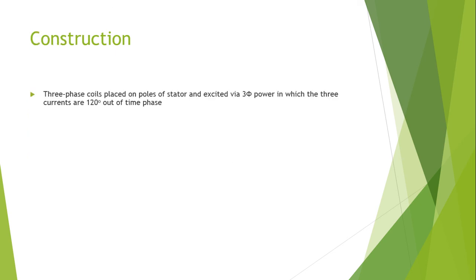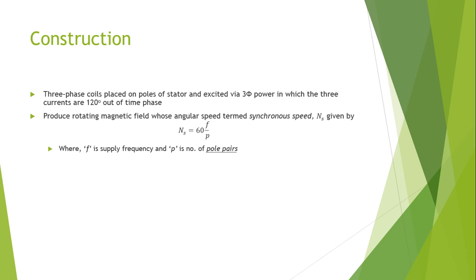Induction generators are available in different sizes and capacities greater than several megawatts. Three-phase coils are placed on the poles of the stator and excited via three-phase power, in which the three currents are 120 degrees out of phase with each other. This produces a rotating magnetic field whose angular speed — the synchronous speed — is given by the formula: ns = 60f / p, where f is the supply frequency.